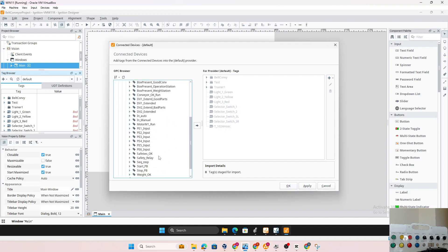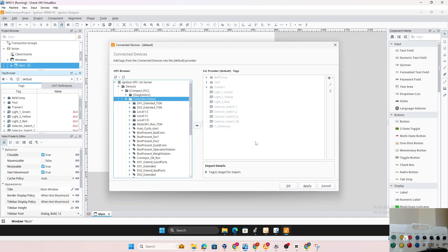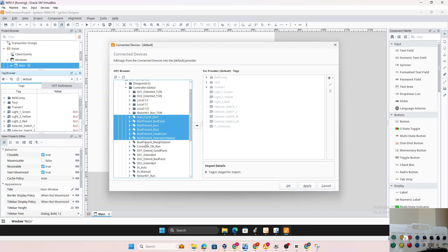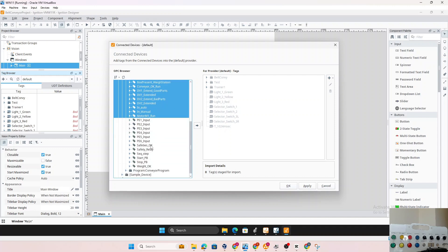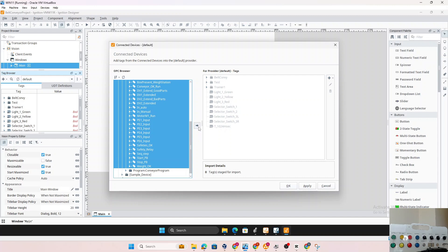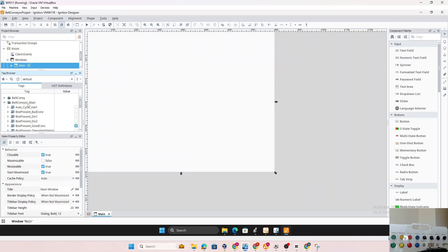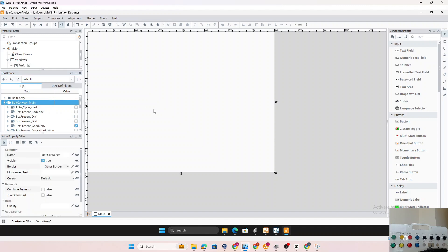We can see all the tags available. We could select all of them and move them to the tag provider, but that's not practical — there could be thousands of tags and we don't want to overload the bandwidth. So we'll only select a few. We'll select tags like 'Auto Cycle Start', use Shift-click to select what we want, and include safety tags. We'll organize them by creating a new folder called 'Main'. All 28 tags are staged for import — once confirmed, a folder is created under Belt Conveyor Main with all tags listed.